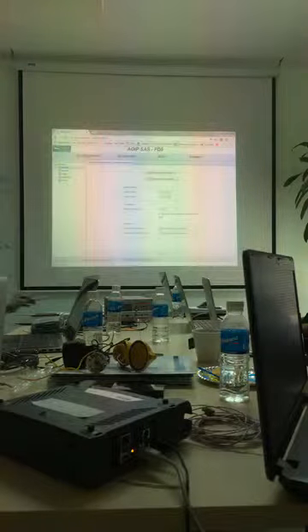So then you go on system. You see, time and date never change automatically with your laptop. For one reason: we are compatible with pharmaceutical norms, 21 CFR. That means every value, even time and date, if you change them, it has to be recorded. So if you record some data, when you extract the data, the result will show that you, admin, changed the data. So then you go on acquisition and you launch your acquisition.